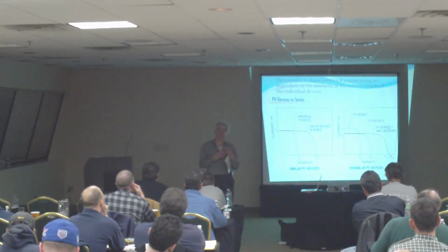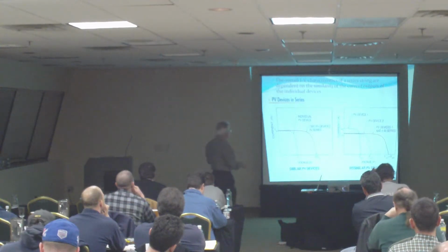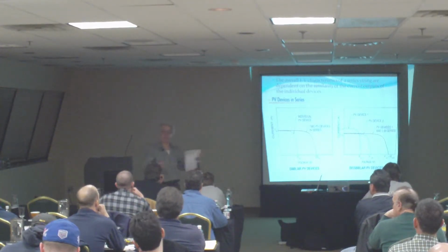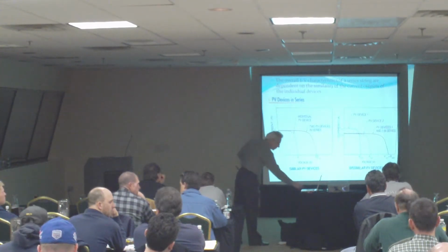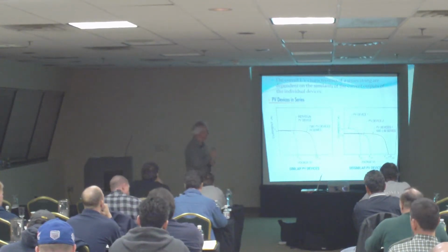So if you start mixing and matching up there, what's going to happen to you? You're going to get voltages that are not per design, so you're going to have to play around with them. But this is the effect. So what am I saying here? Don't buy a Mitsubishi one like this and then go get another one up there, and because they're the same size, slap them all together, and now you say, oh gee, now what happens? If you have to do it, you have to do it, but that's the requirement. There's nothing in the code that says you cannot mix and match. And you know, being electricians, we become very creative in a lot of things.